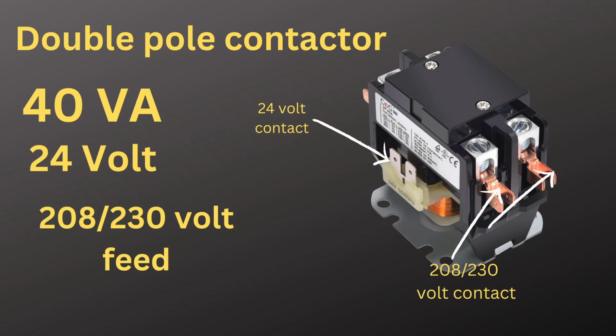And for a dual pole, it's the same thing. It's still 40 VA, 24 volt. Still has the same contact. As you can see if you look down there, it says 24 volt contact. It even has it marked on it. It's still a 208, 230 volt feed, and it's still identical in every way. The only difference between them is that one, single pole, has a single point of contact. The other one, dual pole, has a dual point of contact.